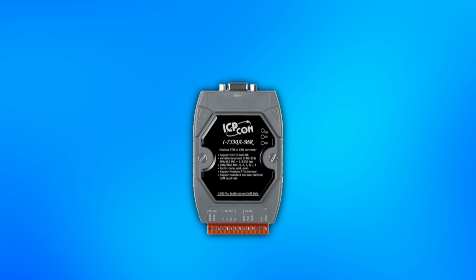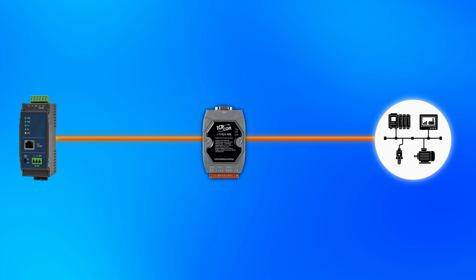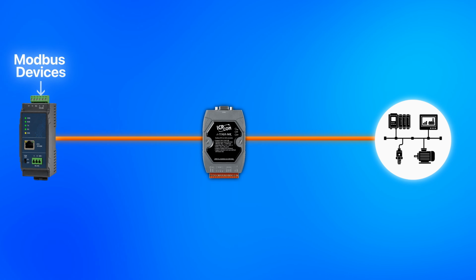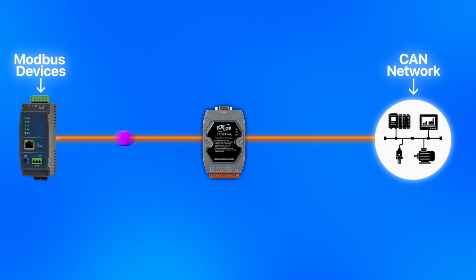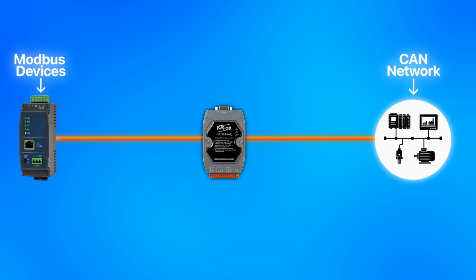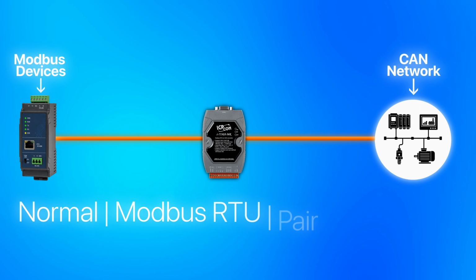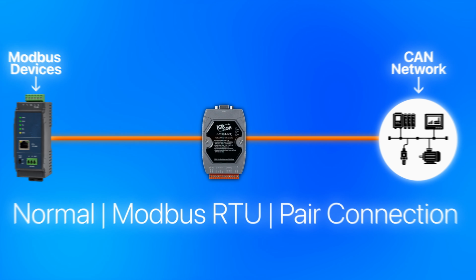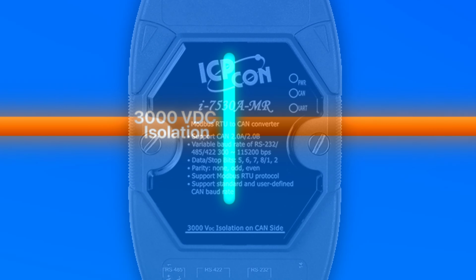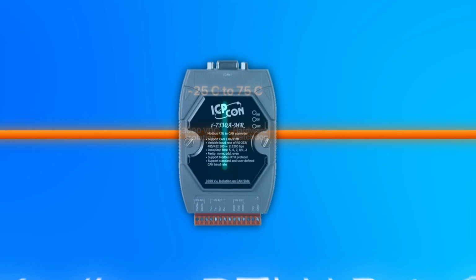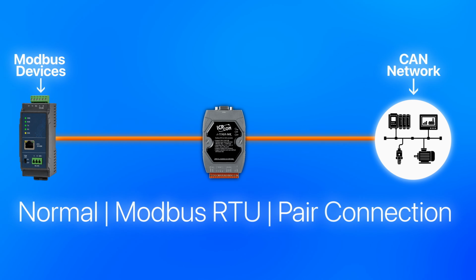The i-7530A-MR is a Modbus RTU to CAN converter that sits between your existing Modbus devices and your CAN network, and it handles the translation transparently. It supports 3 communication modes: normal, Modbus RTU, and pair connection, so it can fit a wide range of integration scenarios. It includes 3000 VDC isolation between the CAN and serial interfaces, a hardware watchdog, and operates from -25 to 75 degrees Celsius for industrial environments. If your PLC or SCADA already speaks Modbus RTU, this is what connects it to the CAN side without touching anything that's already working.